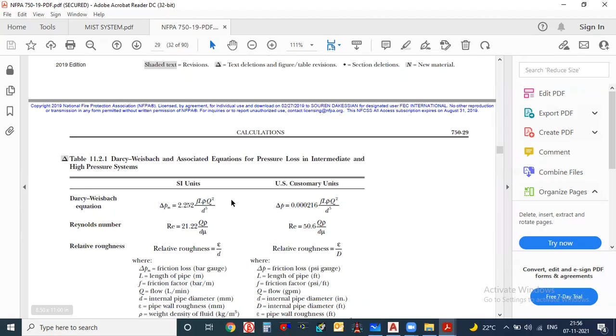This calculation, even I don't know, but here they have given one thing. Hydraulic calculation shall be permitted to be performed using the Hazen-Williams calculation method for intermediate and high pressure having a minimum 20 mm pipe size, provided that the maximum flow velocity through the system piping does not exceed 25 feet per second. So this point is telling that you can also use Hazen-Williams. Once Hazen-Williams comes, just understand that whatever we have seen in the manual calculation, we can also perform in Elite software, because Elite software is also mostly based on the Hazen-Williams calculation only. So this point is telling that you can go with the Elite method also.